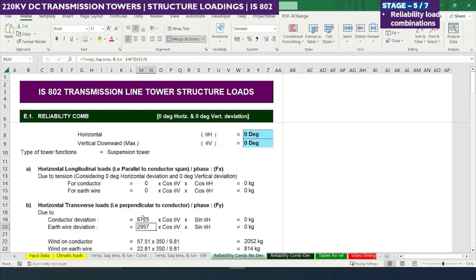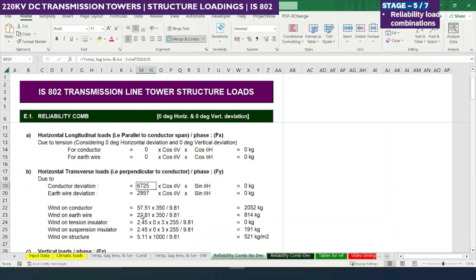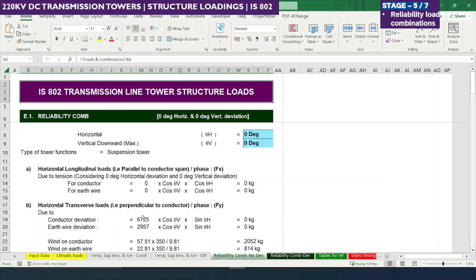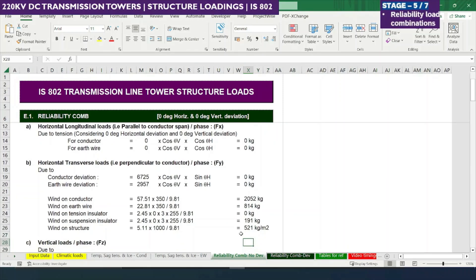Next are transverse loads, perpendicular to the conductor span. Since there is no conductor deviation — zero degrees — the cos vertical angle into sine horizontal angle term is also zero. Similarly for earth wire there are no deviation loads. The next components are wind on conductor, wind on earth wire, wind on tension or suspension insulator, and wind on structure.